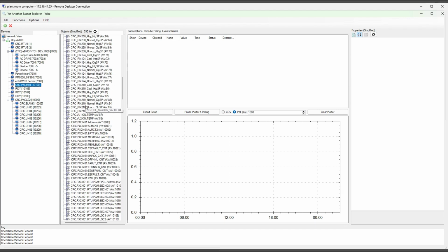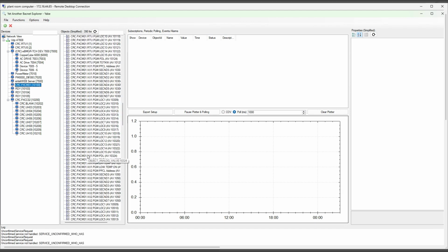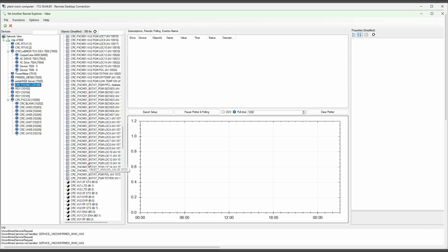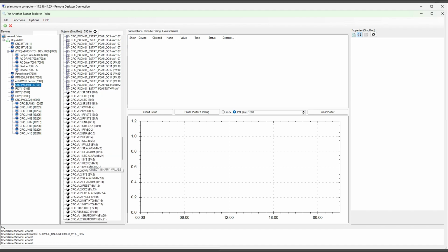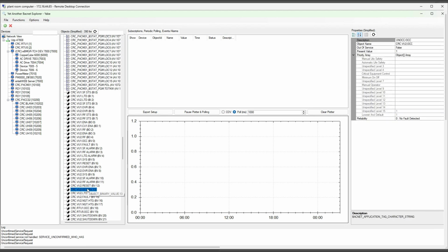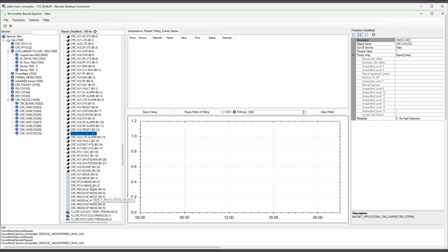You can see this list, like I've already gone through and got all the sort of user-friendly names for all these. And that gives you the ability to find, say, something that's relevant to changing the air temperature in the room, and looking to see what's the current status of what the system is telling it to do. So right now, you can see this is saying that occupied is false. So that means the schedule or the system is currently telling this room that it should be running in unoccupied mode.